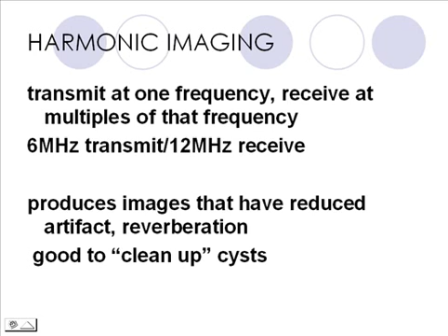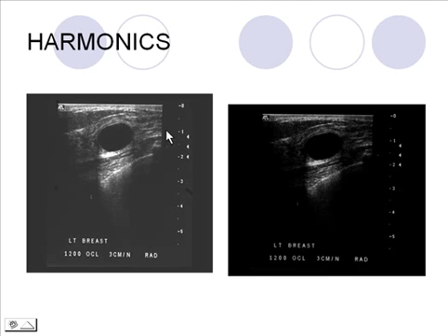I'm sorry if this image is a little dark, but if you had questions about whether there were internal echoes, as long as your background fat is that charcoal or flannel gray, and you put on the harmonic imaging, you can make those artifactual echoes go away. So the point of harmonics is to make artifactual echoes go away. Now, of course, you can make echoes go away by inappropriate gain settings, turning the gain down, but as long as your gain settings are appropriate from the start, that's when you add the harmonics.